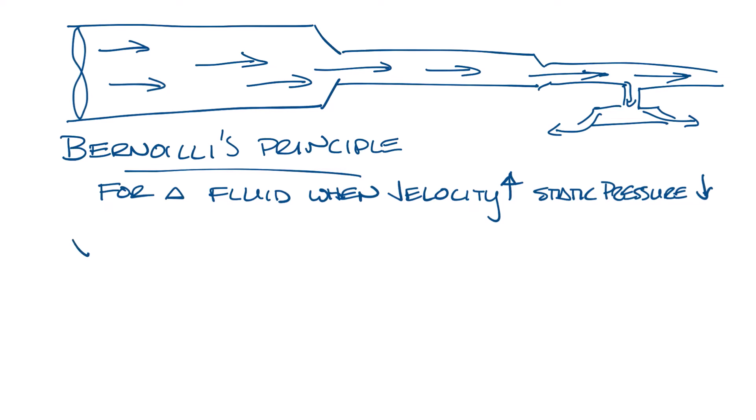You can see that in the pressure equation: velocity pressure plus static pressure equals total pressure. For any given total pressure, if the velocity increases, the velocity pressure will increase, and the static pressure will have to decrease to keep the same total pressure.